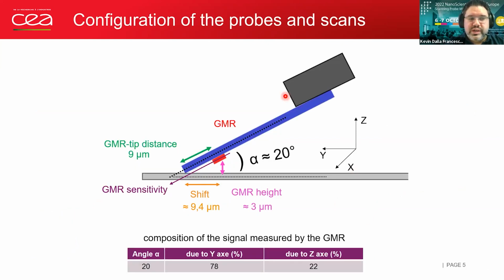So here is a diagram of the measurement made by MRSPM. The measurement of the topography is done with the apex of the cantilever. We don't have a tip under the cantilever. And in red is the position of the GMR on the cantilever, which shows the shift between the topography and the magnetic mapping. This shift depends on the angle of the cantilever with the surface, basically around 20 degrees, and the distance between the end of the cantilever and the position of the GMR, classically around 9 micrometers.